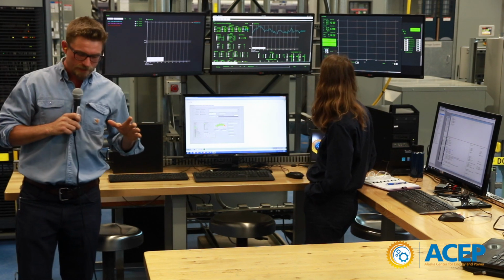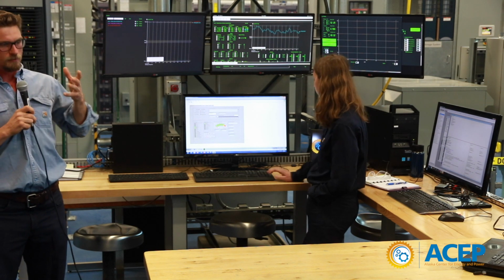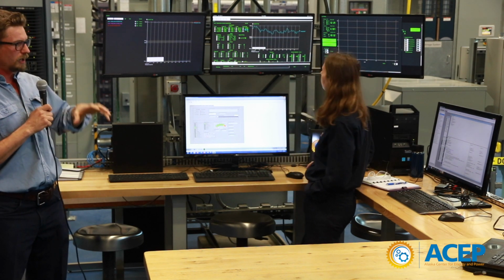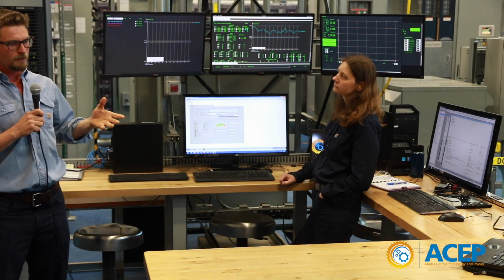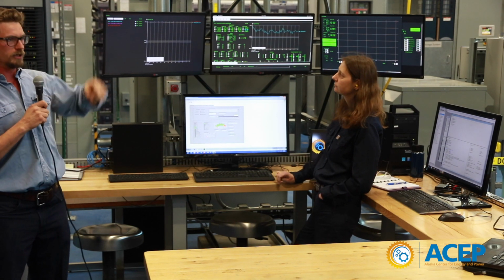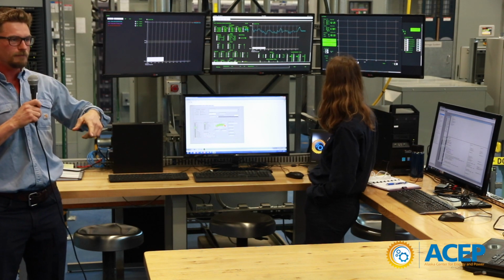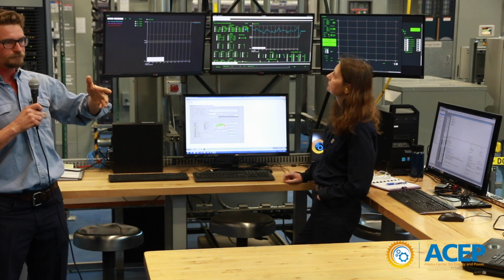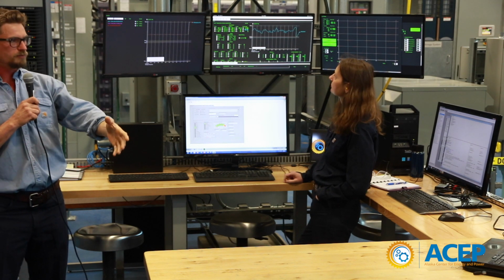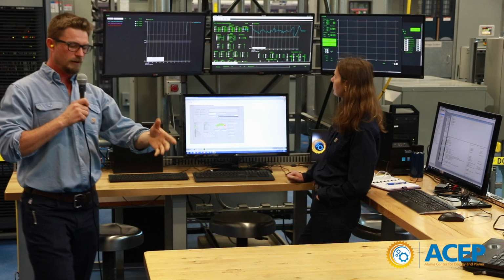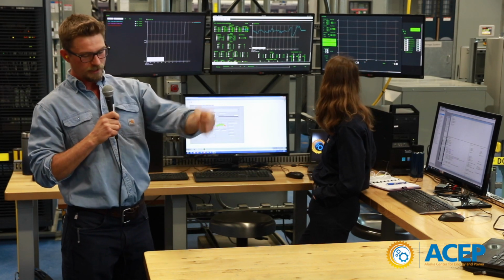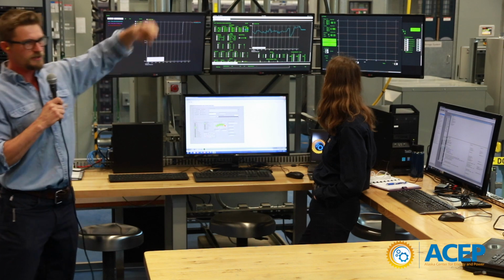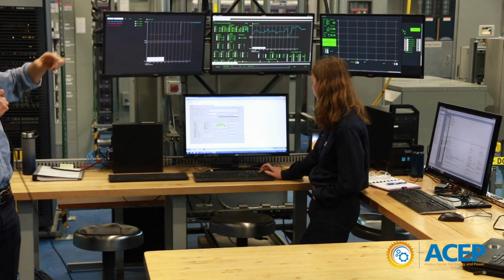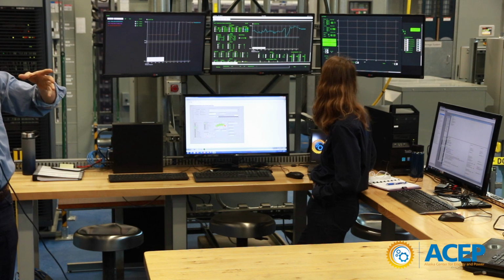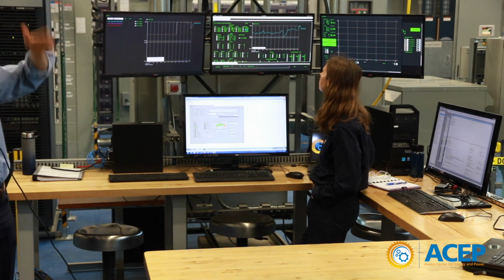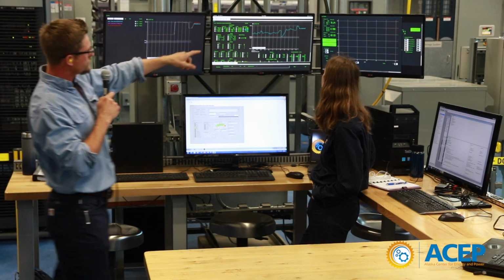So it's holding a pretty tight window, which you'd expect since the load isn't doing anything. But since we're in a small microgrid, a small system with only a couple hundred people, there's a lot of variability in our load. It ramps up and down a lot over a short time scale, because when someone turns on a 1 kilowatt water boiler, you see that in your whole load system. There's not a whole lot of averaging to balance out the load, so there's a lot of short time scale variability, and that affects your grid frequency.